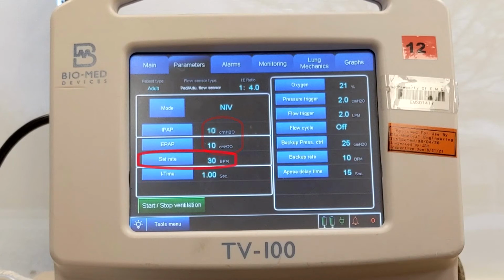When providing CPAP in this mode, the rate should be set to 30 breaths per minute or 60 breaths per minute so that the ventilator updates the CPAP value every 2 seconds or 1 second, respectively. If the apnea delay interval is exceeded due to a rate set lower than the apnea delay time and there is no patient-triggered breath during that time, then the TV-100 will detect apnea. The TV-100 will ventilate per the configured apnea backup settings, and the apnea alarm will actuate. The apnea backup feature can be disabled by turning off the backup rate.